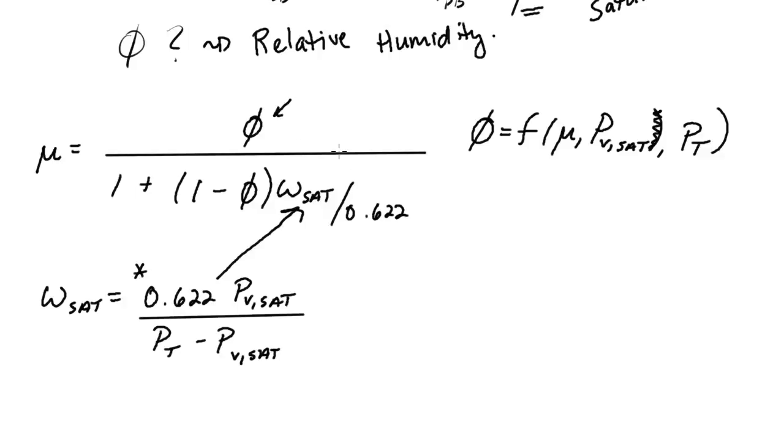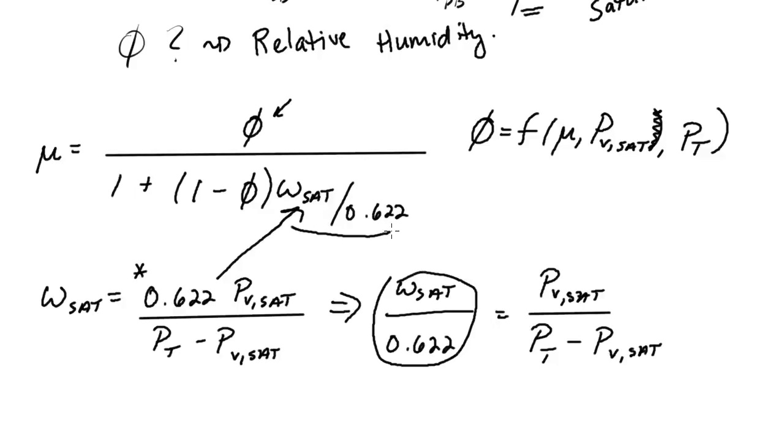Now, this is a little convoluted on the algebra, and if you look in the fundamentals, it's not exactly clear how to do this. So I'll actually work through this step by step so you can see where that final formula in the ASHRAE fundamentals comes from. If I divide this equation both sides by 0.622, I would get omega saturation over 0.622 equals partial pressure of the vapor at saturation divided by total pressure minus PV sat. So we have this fraction here that's the same fraction we have here, so we can replace this with this term.